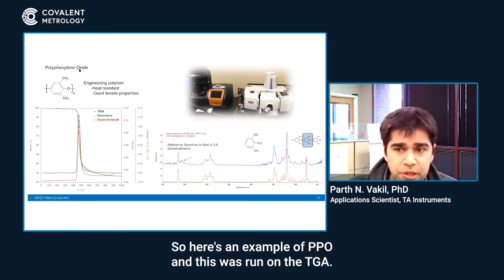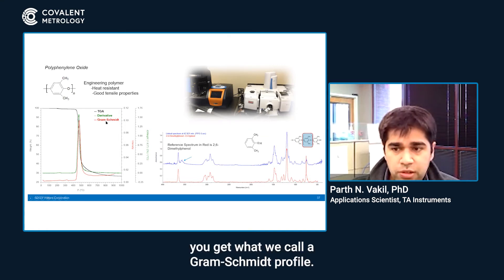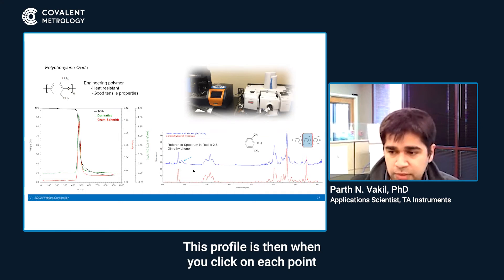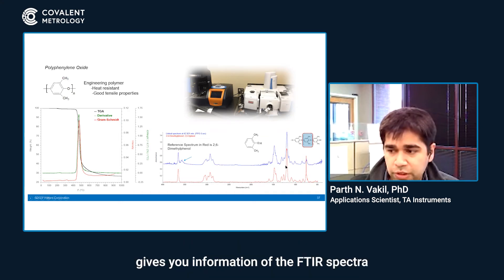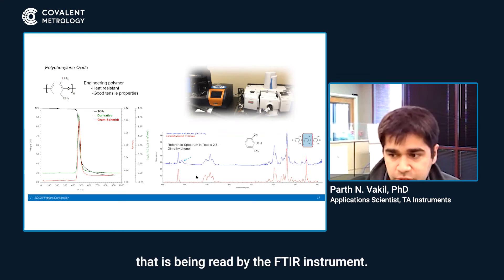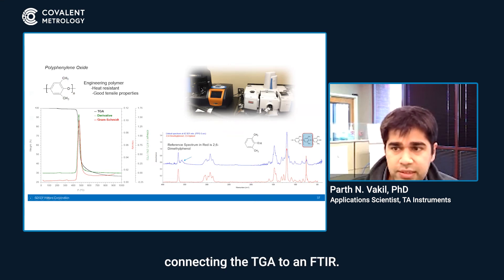Here is an example of PPO, which was run on the TGA. When you do TGA-FTIR, you get what we call a Gram-Schmidt profile. When you click on each point of this profile, it gives you information on the FTIR spectra being read by the FTIR instrument. This way, you can get a lot more insight by connecting the TGA to an FTIR.